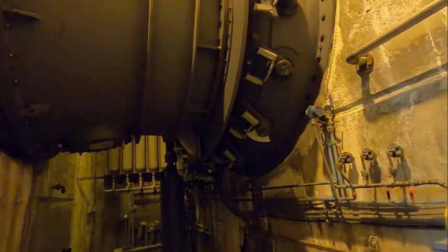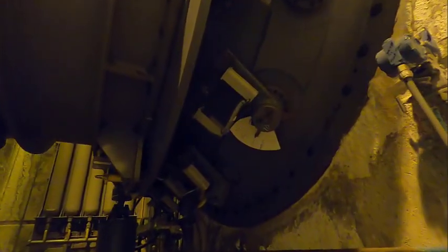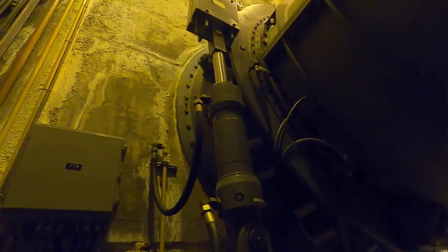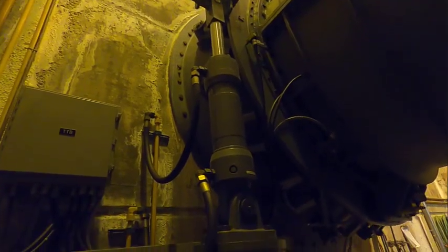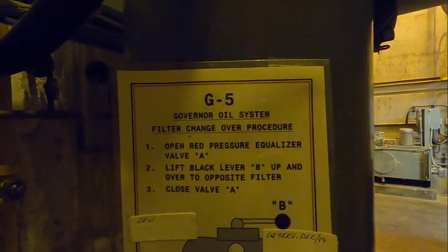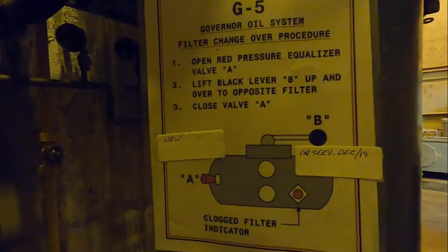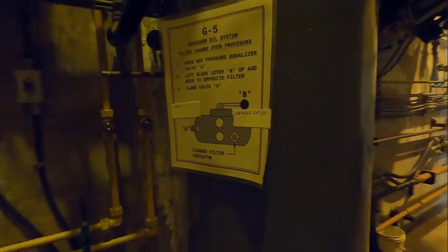We are about to walk underneath the turbine. You can see the wicket gate linkages there, and attached to them is a scale that shows us how open they are. If we look closely, we can see that the gates are open 75% right now. We are looking at the hydraulically actuated governor that controls the wicket gates from being completely open to being completely closed. And here is a standard operating procedure for changing out the oil system filter.